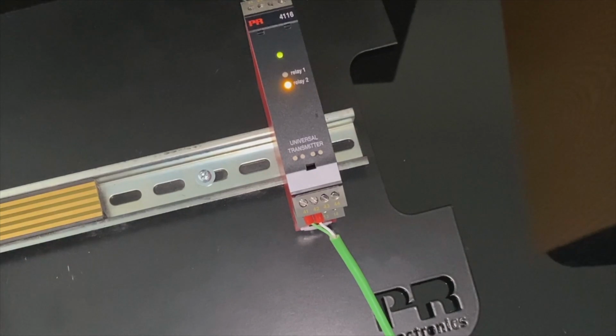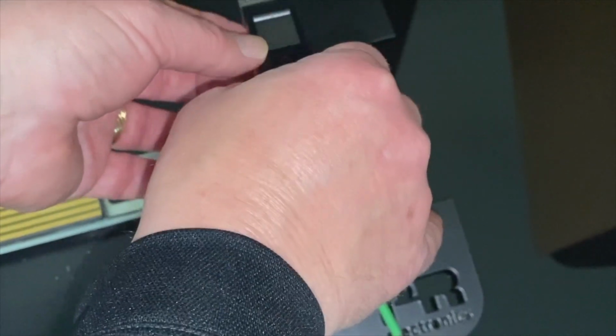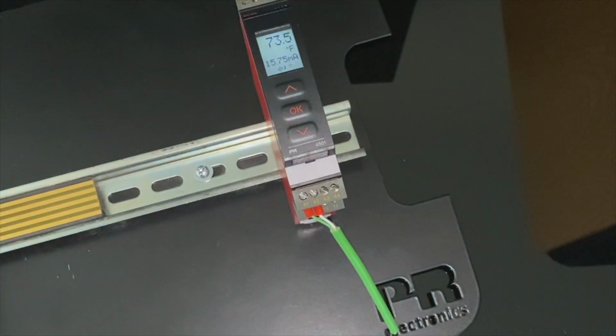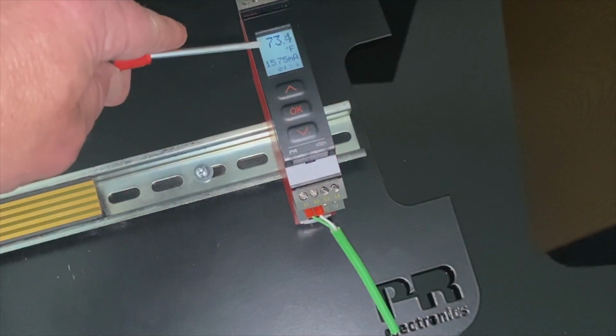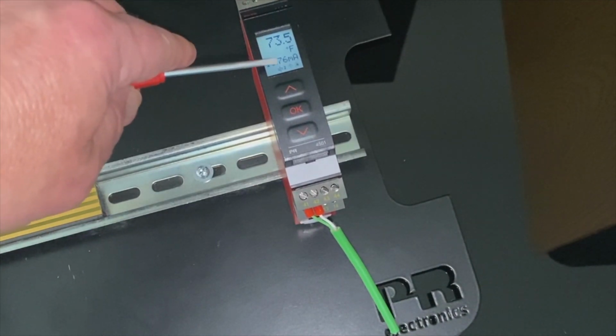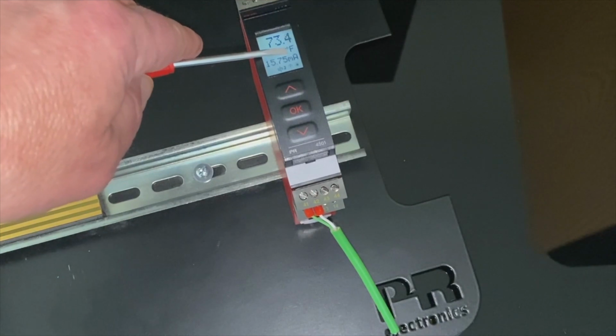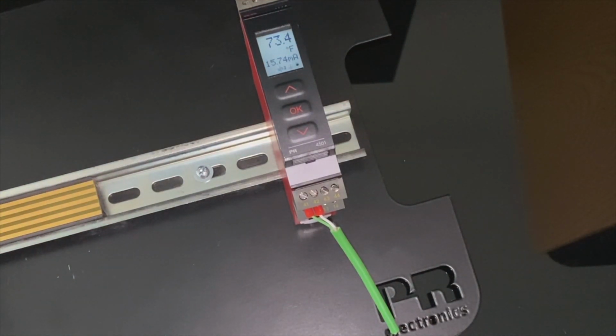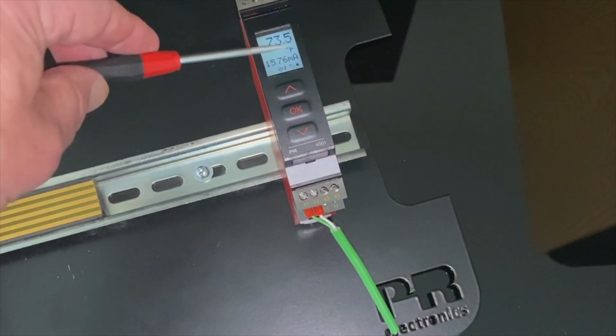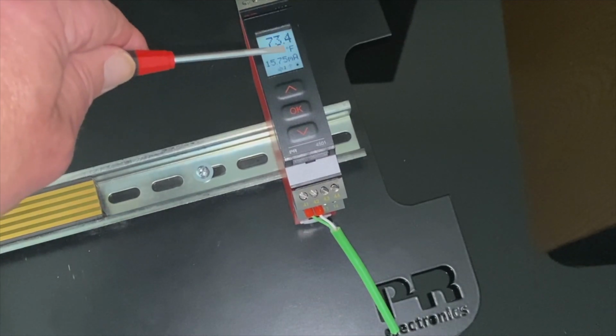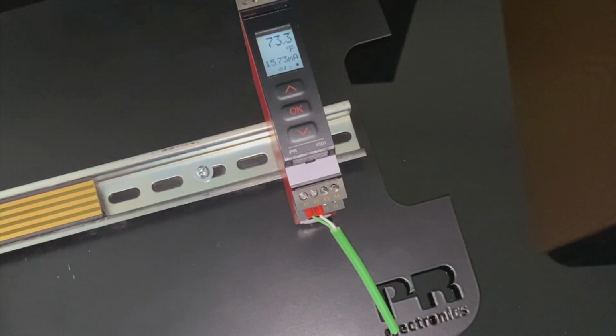So once you've shown the diagnostic capabilities of the LEDs, now it's time to work with our 4501, our configurator. And as you'll see, it also serves as a local display. Very important point. A lot of customers would like to see that. Some don't need it. But on this screen, as your display, you're seeing the value in the engineering units that he desires, and know that there are 70 different engineering values in the 4116. So if you're taking a current, you're trying to measure level, flow, you can easily find that value, and once you use that as a local display, the customer will be looking at the engineering units he wants to see.